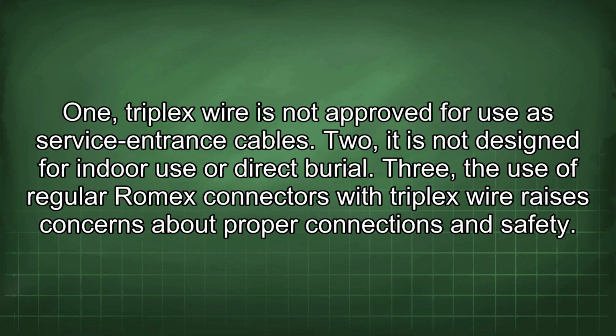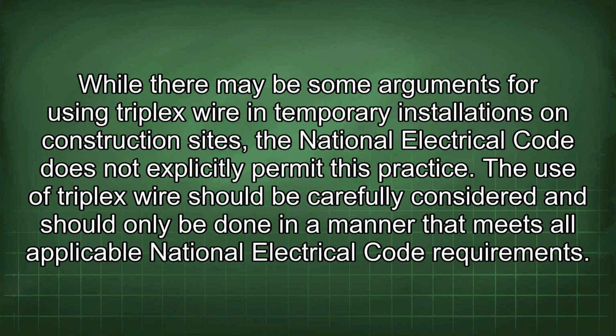1. Triplex wire is not approved for use as service entrance cables. 2. It is not designed for indoor use or direct burial. 3. The use of regular Romex connectors with triplex wire raises concerns about proper connections and safety. While there may be some arguments for using triplex wire in temporary installations on construction sites, the National Electrical Code does not explicitly permit this practice.